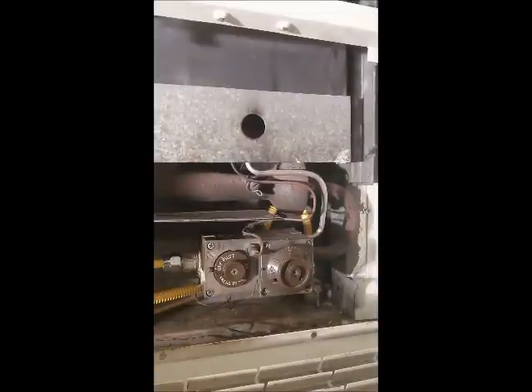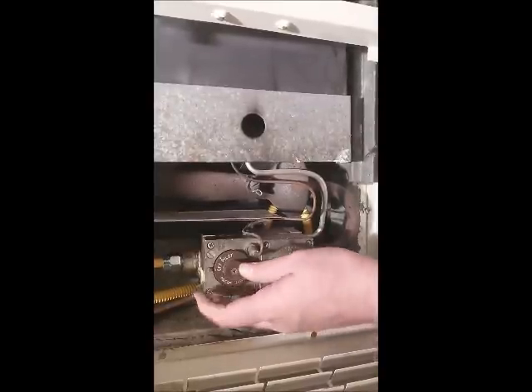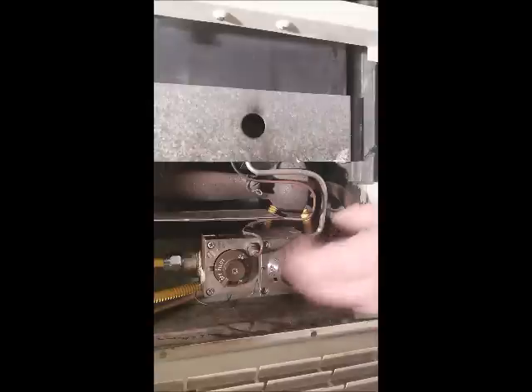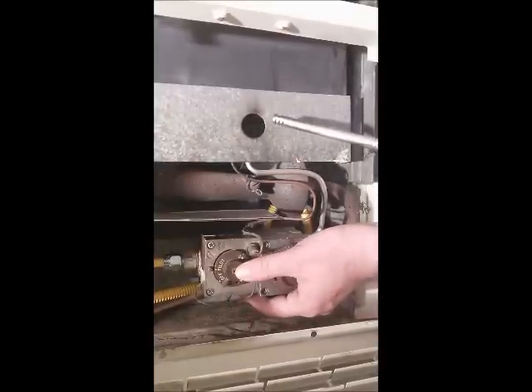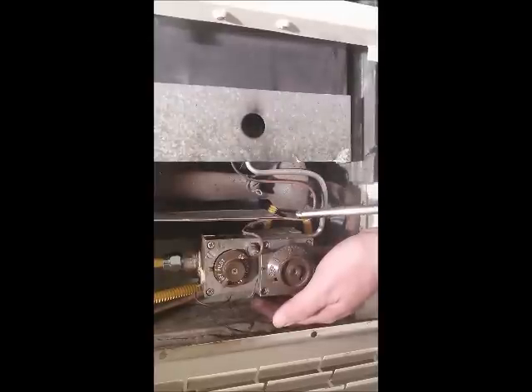These dials typically depress inward to turn, so I'm going to turn it inward to the pilot position. There isn't actually any gas feeding the pilot unless I depress that button. So I'm going to depress the button and light the pilot light at the same time, then hold the pilot button down until there's enough heat to register with the thermocouple to tell the valve that the pilot light is actually on.